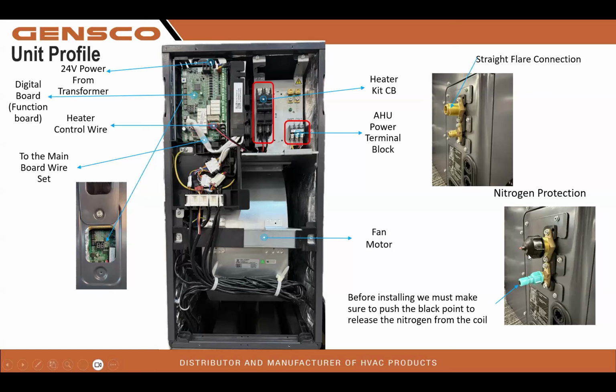And you'll notice these caps right here on our flares. We simply depress this little black button here on our liquid line to let that nitrogen out. And then you're merely going to spin these caps off and start connecting your line set. So just depress this little black cap, let that nitrogen out, and those keepers will come right off.